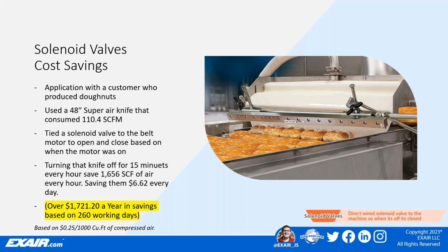On average, they calculated that for every hour of production, the glazer belt was off for 15 minutes. So turning that knife off for 15 minutes every hour saved 1,656 standard cubic feet of air for every hour, saving them $6.62 every day and over $1,700 a year in savings based off of their 260 working days.